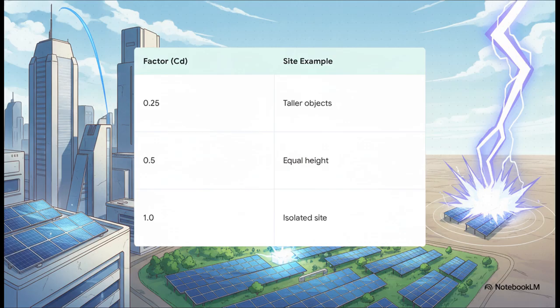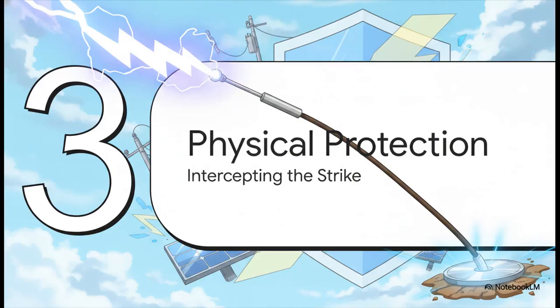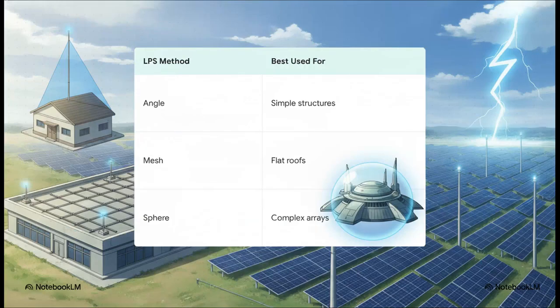You are taking the full, unfiltered statistical probability of a lightning strike. All right, Section 3, physical protection design. If you need it, how do we physically intercept the strike? The standard gives us 3 valid methods to design our air termination system. That's just a fancy term for the physical rods catching the lightning. You've got the protection angle method, which is solid for simple single buildings. You've got the mesh method, which is fantastic for flat roofs. And then you have the rolling sphere method, perfect for complex geometries.